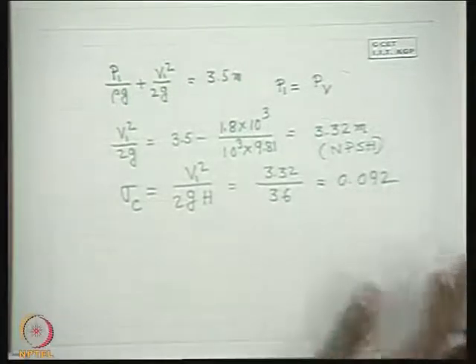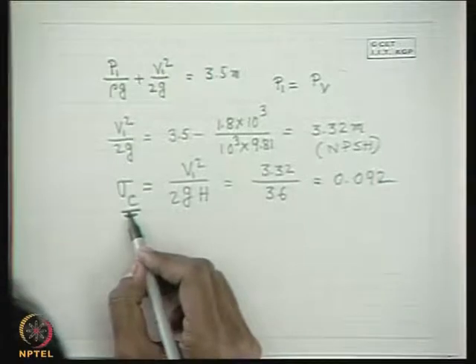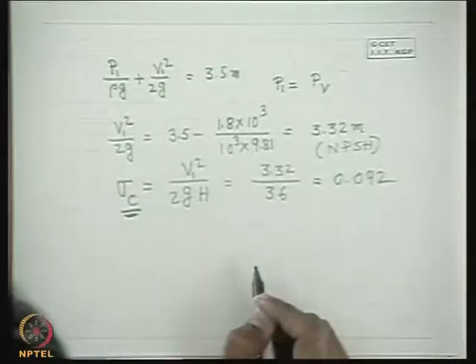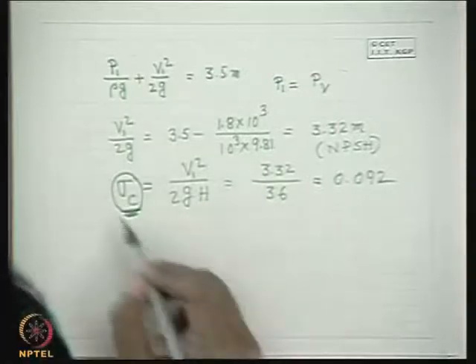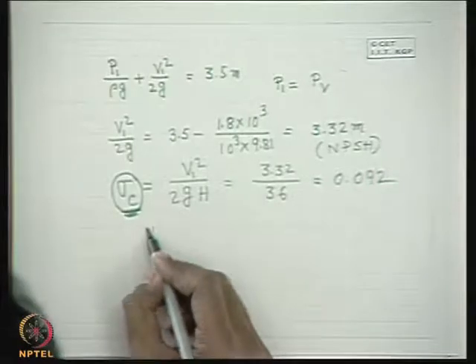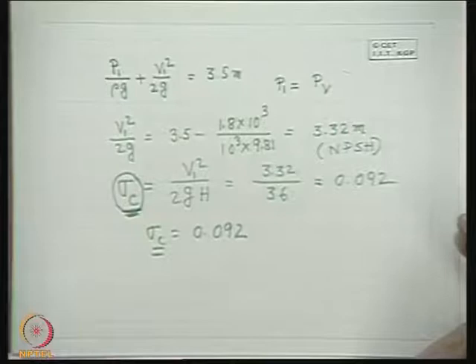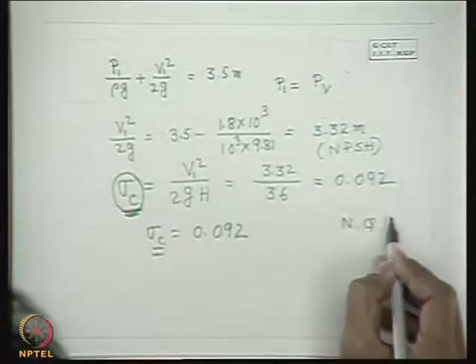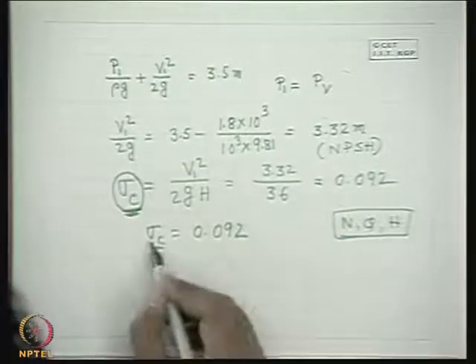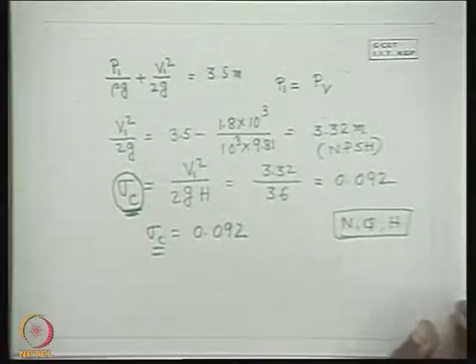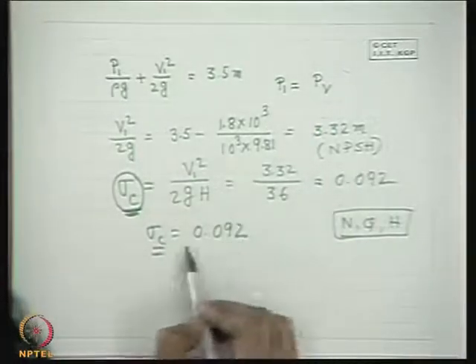The critical cavitation parameter σ_c is a dimensionless quantity that depends upon pump speed, discharge, and head. When discharge, head, and speed are constant, this dimensionless parameter — representing a similarity criterion — remains the same for the second case also. It will not change unless the specific speed changes, because σ_c is a function of specific speed. So long as N, Q, and H remain the same, the pump operates at the same specific speed and σ_c is unchanged.